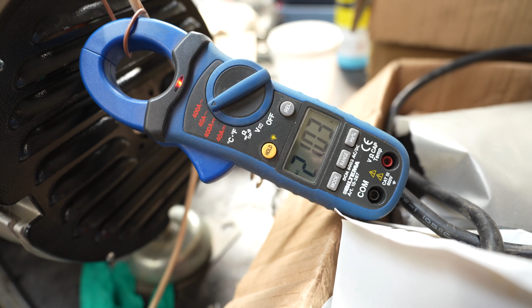As you saw, with the pedal to the metal, we were drawing 21 amps. That is 21 amps at 240 volts, so that's something like 5 kilowatts. But I don't want to torture the itty bitty Perkins. I like it, I don't want to hurt it. So we'll probably load it somewhere at around 4 kilowatts instead. That seems to be much better for it.